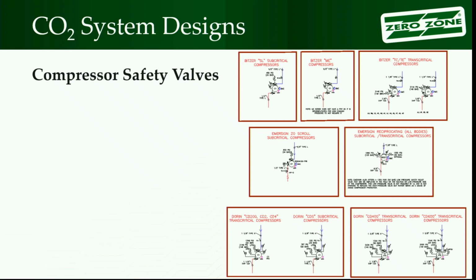Bitzer safety valves on the low pressure compressors, their safety valves are isolatable. If you back out the valve they're on all the way, it'll backseat that valve, and that safety valve is not protecting that compressor at that time. As a result of that, we and other manufacturers put a safety relief valve in the suction line. So if you back the valve out all the way and the pressure goes up, that safety valve will release.